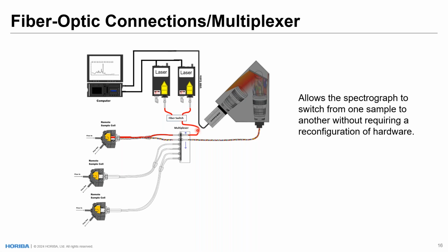the light from the laser is interfaced into the multiplexer, and then from here, the multiplexer can send the laser light out to various remote sample cell points, excite and vibrate the molecules, and collect the Raman spectra back through a fiber optic cable into the multiplexer. And then this is read from the multiplexer back into the spectrograph, where that image is read onto our camera. And then that spectrum is brought from our spectrograph camera through a serial connection into the computer.